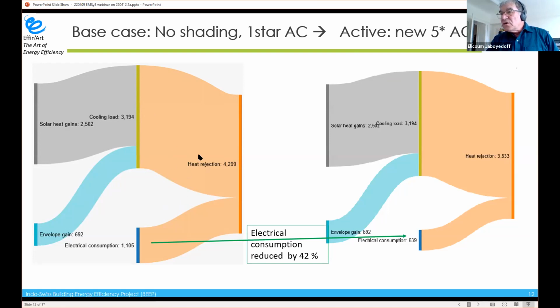Now if you look at the heat rejection, that means what is going out from the compressor and the air cooler, then the electrical consumption for the cooling, to remove this cooling load, of the AC is 1100 in this case. Now, if you switch to the 5 star, then what happened? You still have the same solar heat gain, the same envelope gain, but you are reducing your electrical consumption by about 42%, without adding shading.